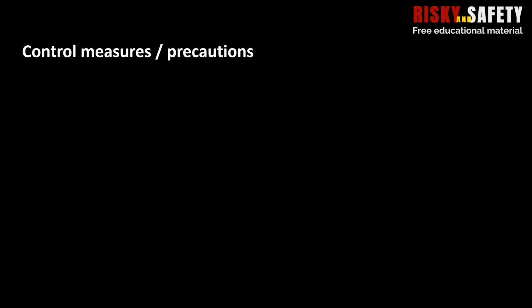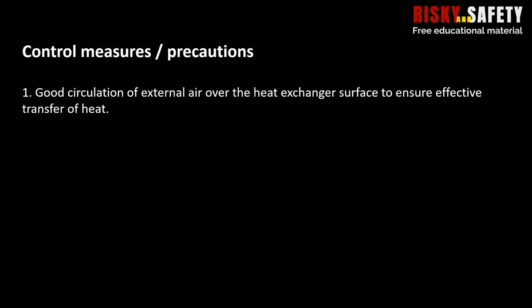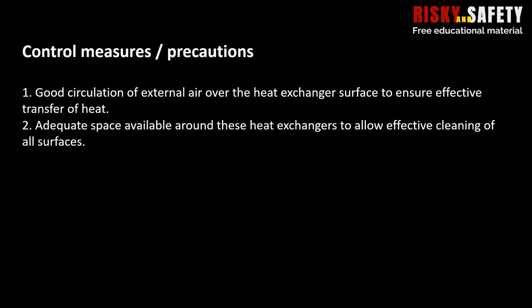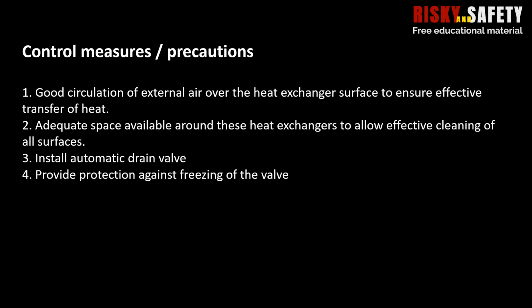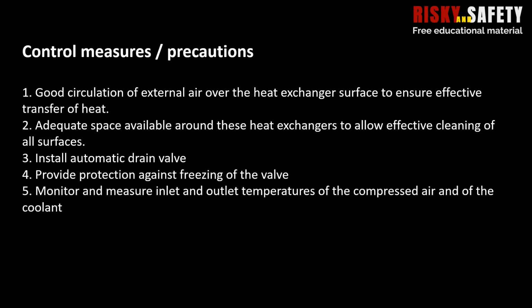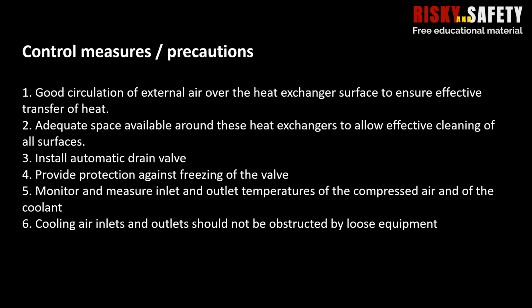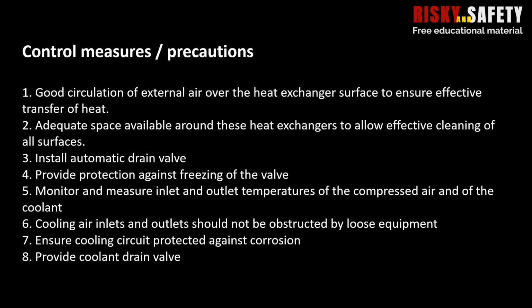You can control the risks by good circulation of external air over the heat exchanger surface to ensure effective transfer of heat, and adequate space around these heat exchangers to allow effective cleaning of all surfaces. Install an automatic drain valve, provide protection against freezing of the valve, and monitor and measure inlet and outlet temperatures of the compressed air and of the coolant. Cooling air inlets and outlets should not be obstructed by loose equipment. Ensure the cooling circuit is protected against corrosion and provide a coolant drain valve.